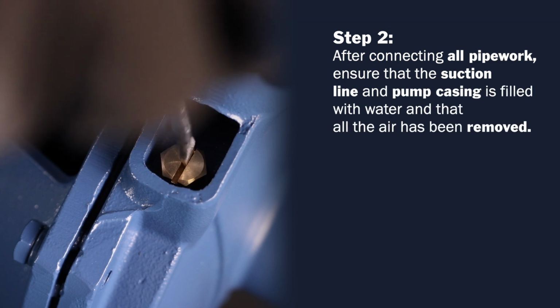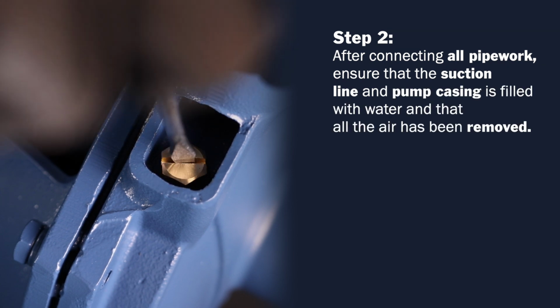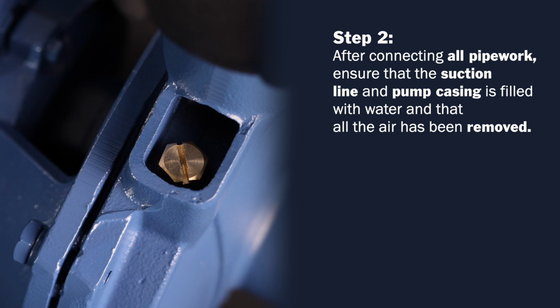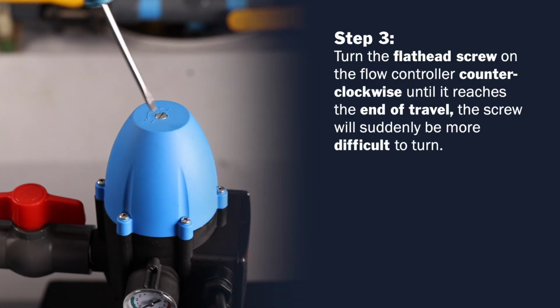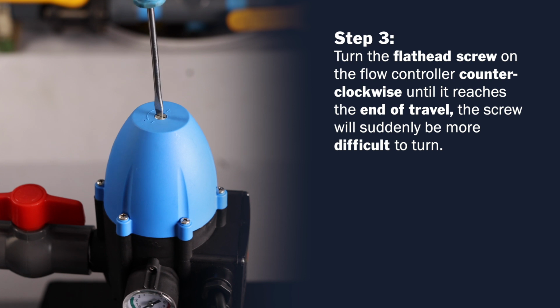After connecting all pipework, ensure that the suction line and pump casing is filled with water and that all the air has been removed. Step 3. Turn the flathead screw on the flow controller counterclockwise until it reaches the end of travel. The screw will suddenly be more difficult to turn.